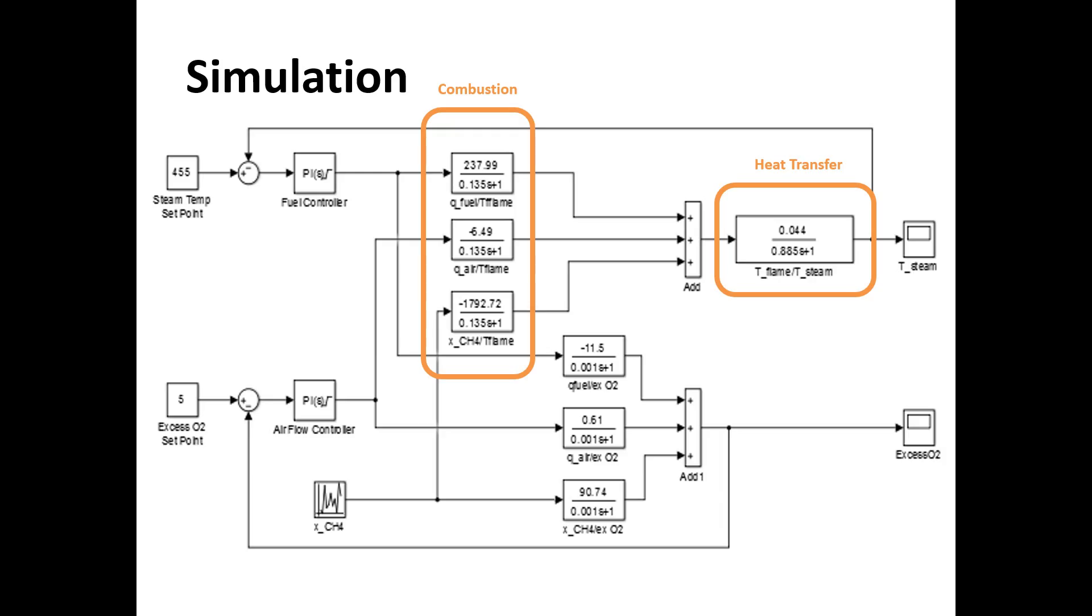This is the top loop which calculates the steam temperature. There was also a parallel control loop which used the excess oxygen models. Then we have the two set points you notice on the left hand side, steam temperature and excess O2.